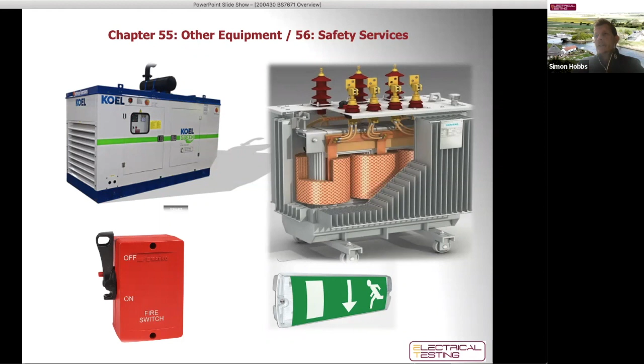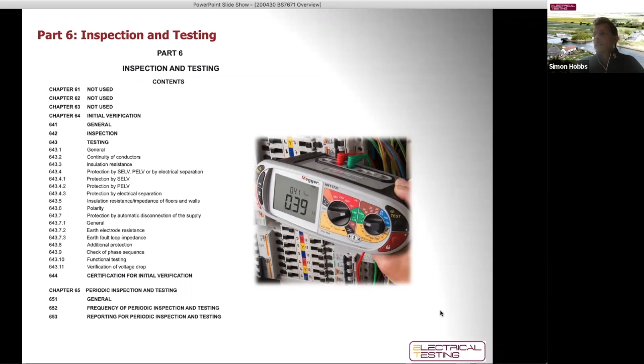Not too many changes, lots of changes in the regulations with the 18th edition. These 3 chapters disappeared and they've now been replaced with chapter 64 and 65. And really grouping inspection and testing into two elements. The first is in chapter 64 called initial verification, and this relates to new installations. I haven't done too much reading out, but I will here because this is incredibly important. We've designed the installation, we've selected the right protective devices, we've followed part 5 and we've selected the right cabling and the earthing, we've installed it. We now need to make sure that the electricians haven't made any mistakes, because believe it or not, we do make mistakes when we install things.